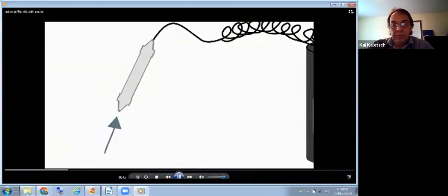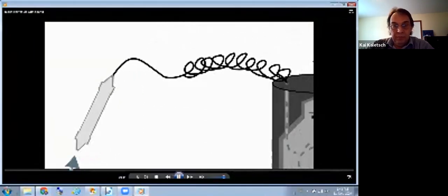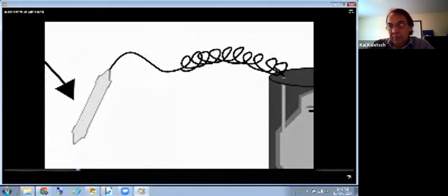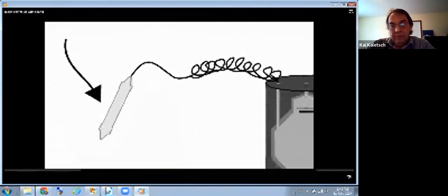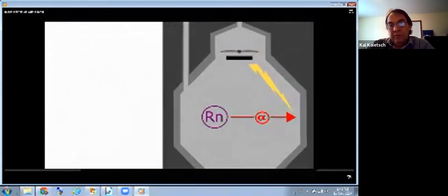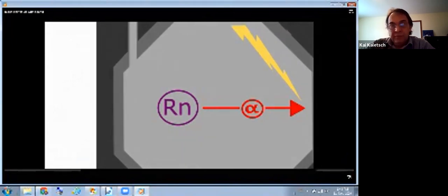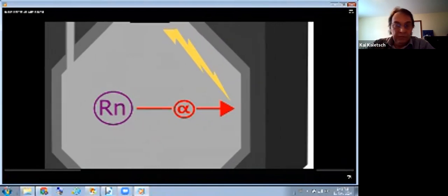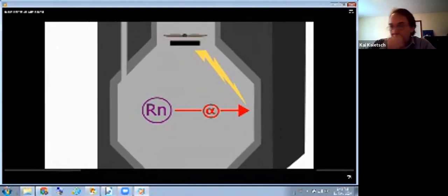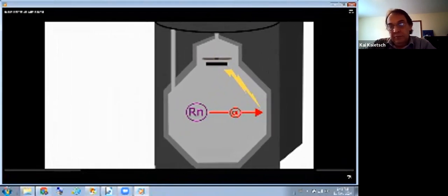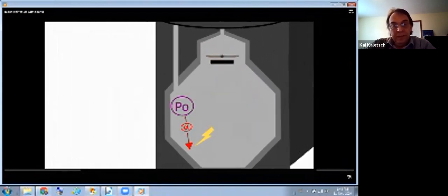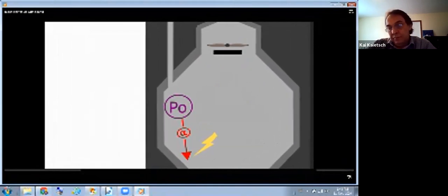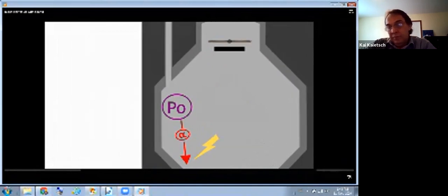The CT007R uses an internal pump to draw air through a scintillation cell. Before air is drawn into the scintillation cell, any radon progeny in the air is removed by a filter. As radon decays inside the cell, the alpha particle emitted hits the wall of the cell, which is coated with scintillation powder, and emits a flash of light. The photomultiplier converts the light into an electronic pulse, which is then counted. The difficulty with using this principle for measuring radon is that the product of radon decay is also radioactive. The radon progeny tends to plate out or stick to the side of the scintillation cell.